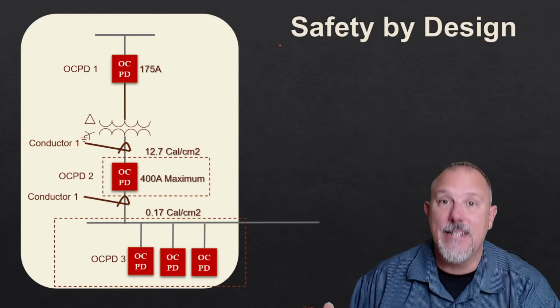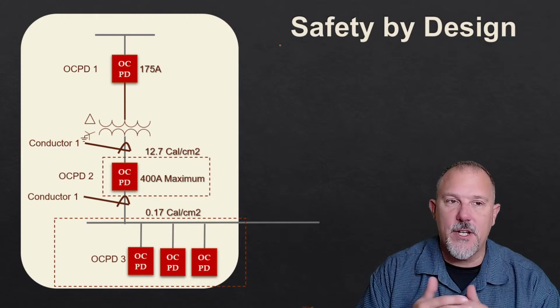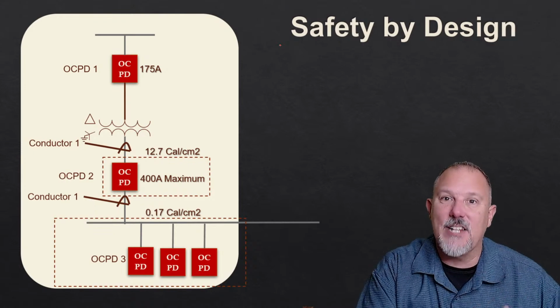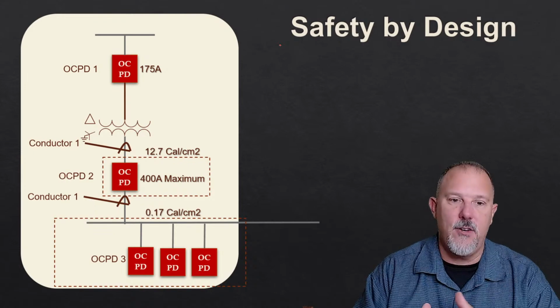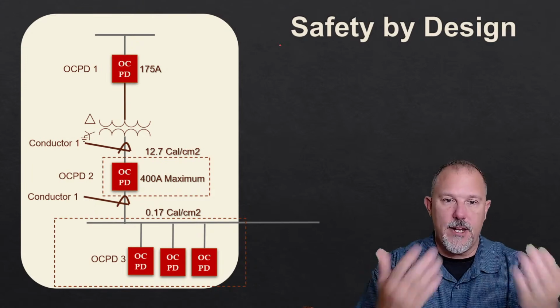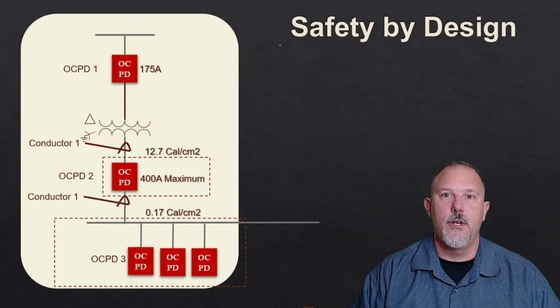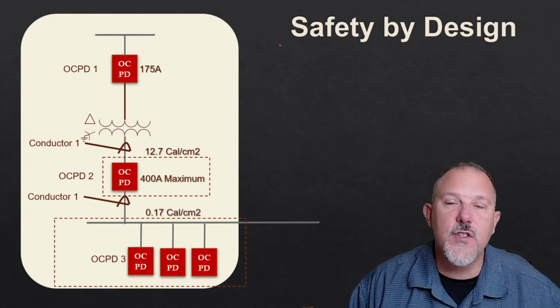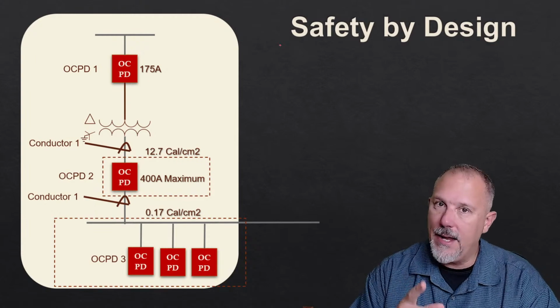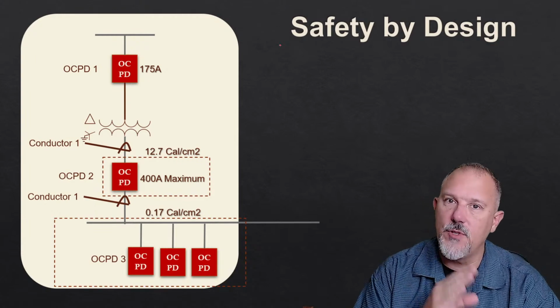And we had to put an exception for the barriers because we said if you're using the 6 disconnect rule, which means in a panel board with 6 disconnects, you're looking at a bare copper bus and 6 breakers. You can't barrier that off. So we had to put an exception in. But we understood the hazard was still there.